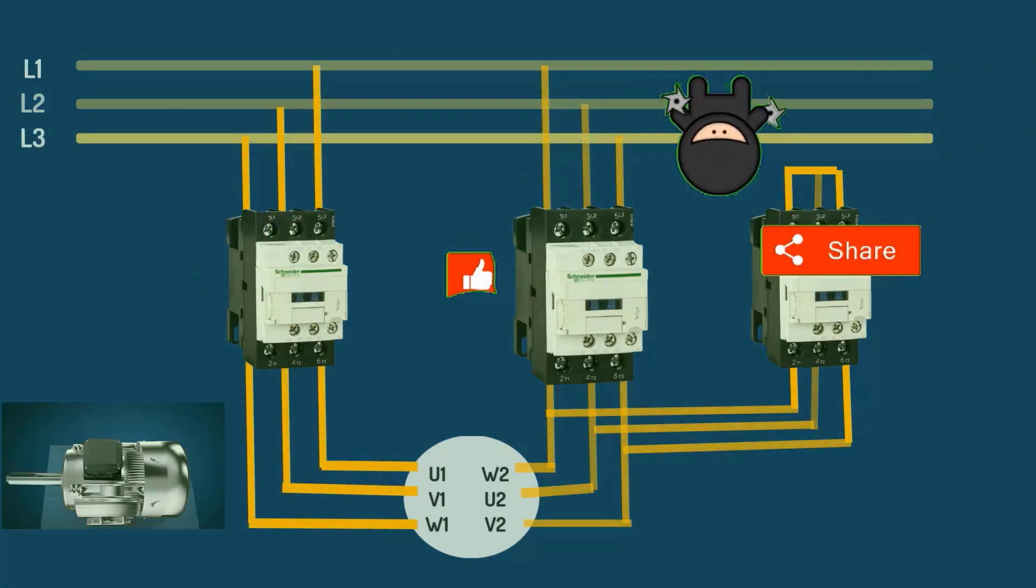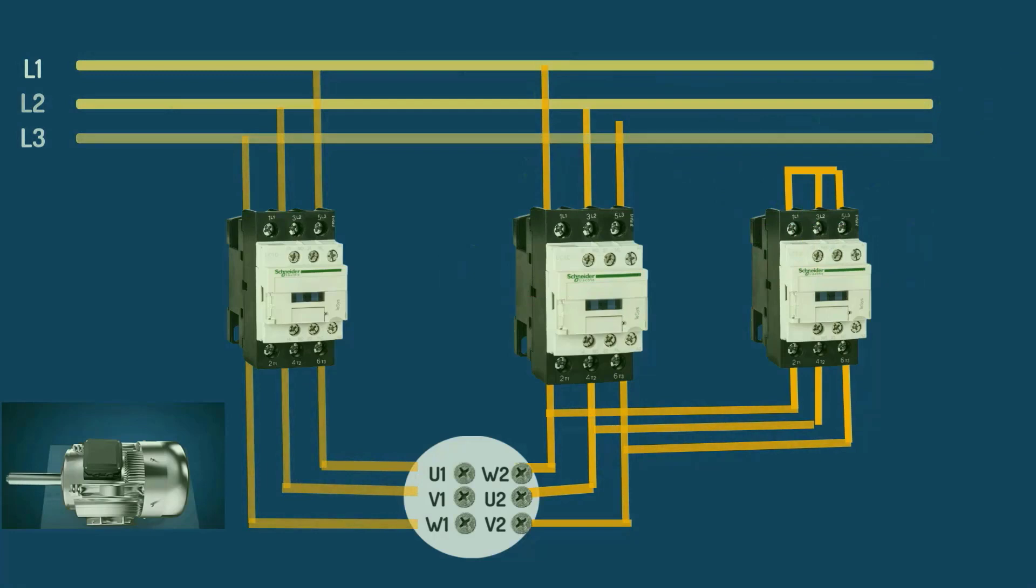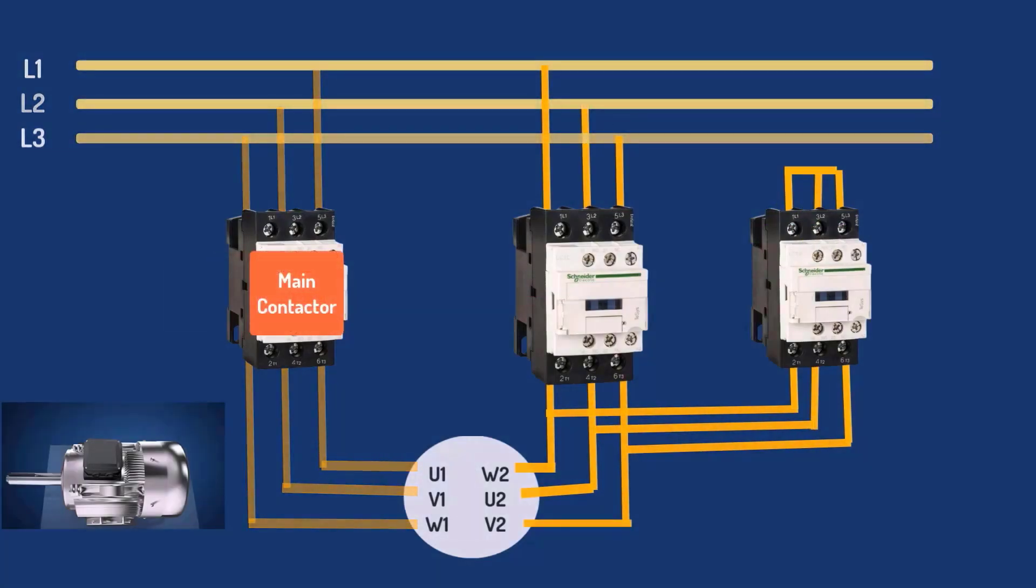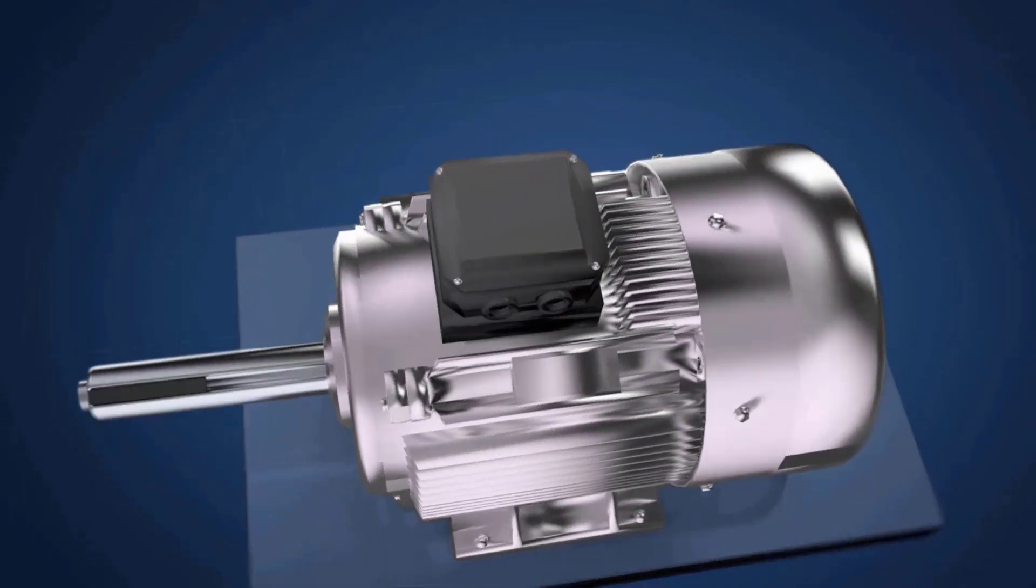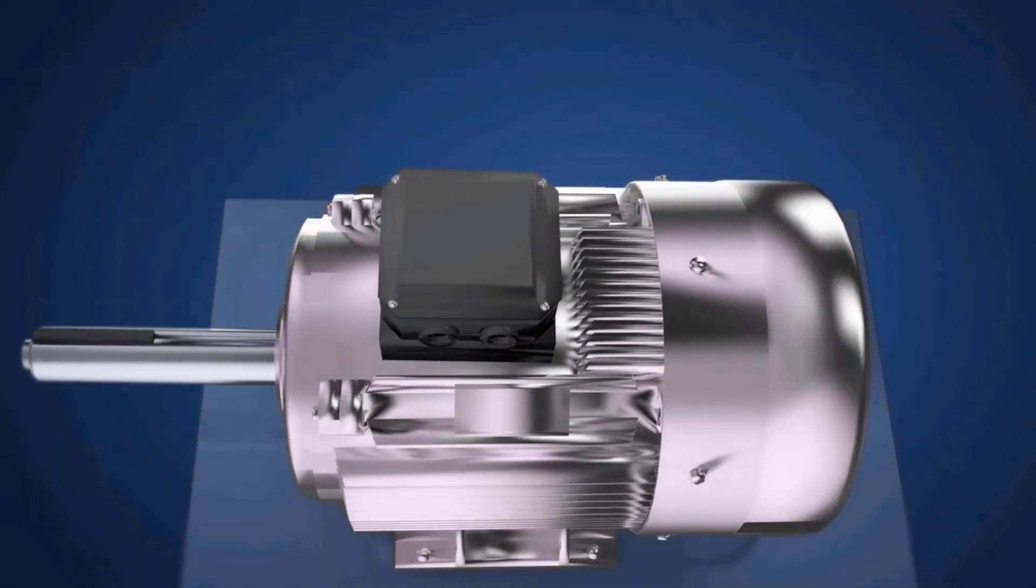Before we understand what a star delta starter is, it's important to understand why we need one. It's okay to start small motors directly, but there's a problem when you start a big motor directly. A large induction motor in delta can produce sudden inrush current of five times its full load capacity when starting up.